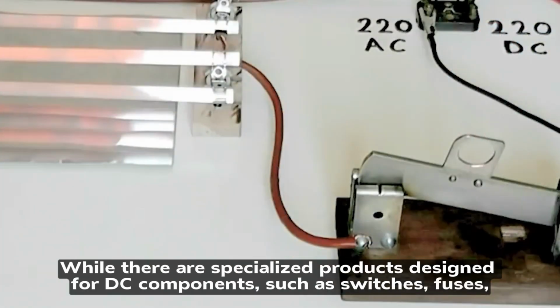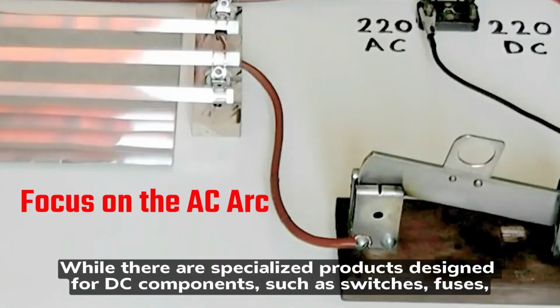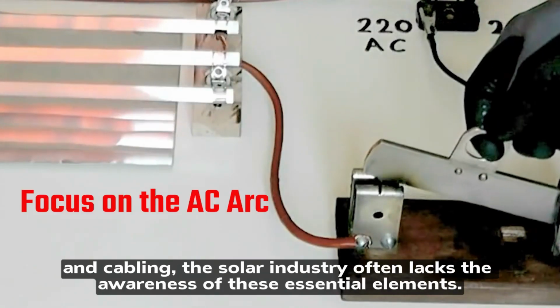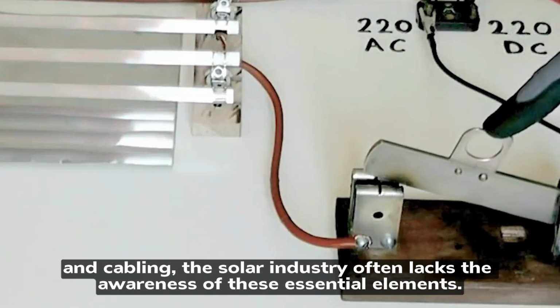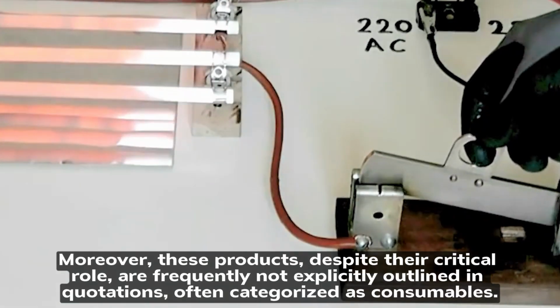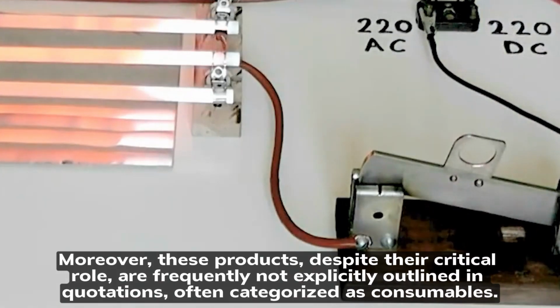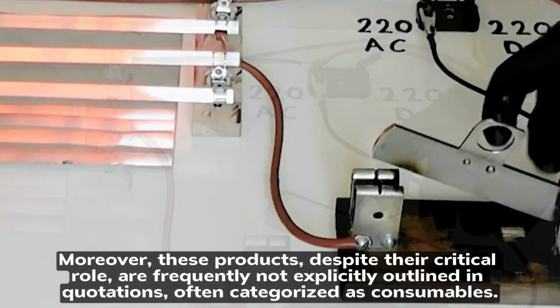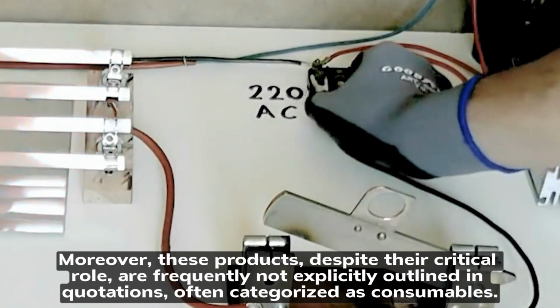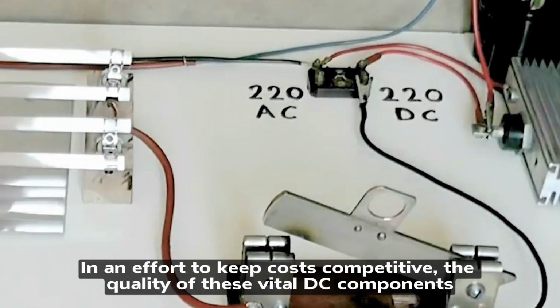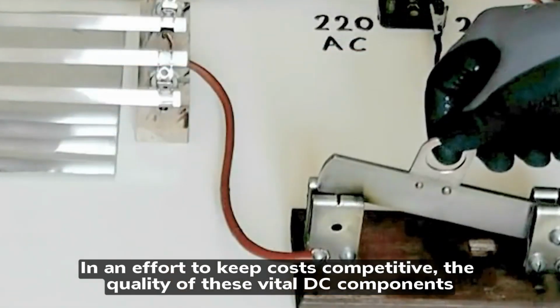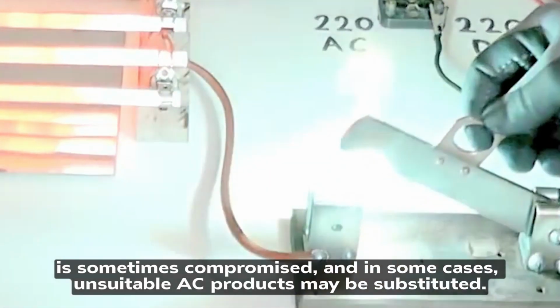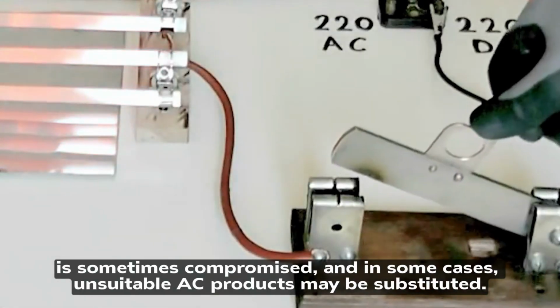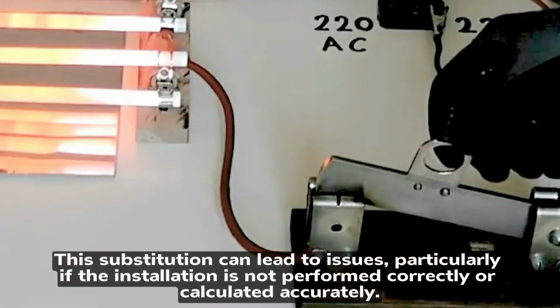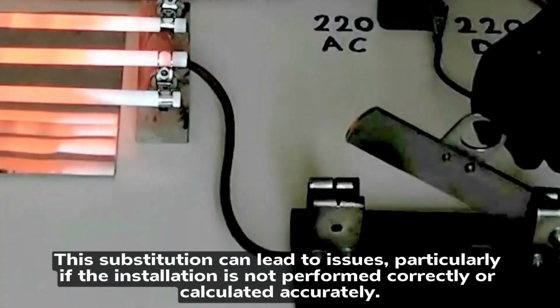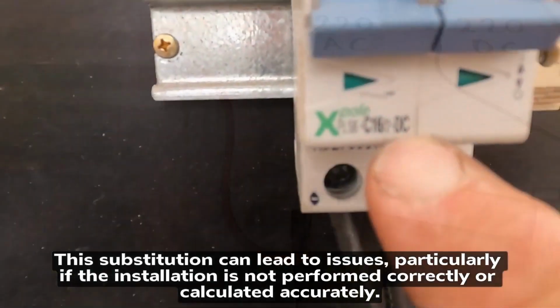While there are specialized products designed for DC components, such as switches, fuses, and cabling, the solar industry often lacks the awareness of these essential elements. Moreover, these products, despite their critical role, are frequently not explicitly outlined in quotations, often categorized as consumables. In an effort to keep costs competitive, the quality of these vital DC components is sometimes compromised, and in some cases, unsuitable AC products may be substituted. This substitution can lead to issues, particularly if the installation is not performed correctly or calculated accurately.